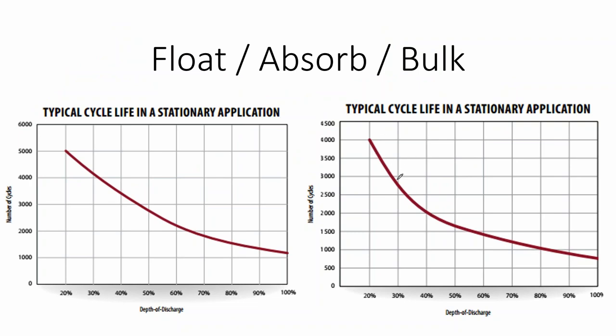If we look at these two batteries in the manufacturer spec, on this lower end battery, you don't want to cycle it down more than about 35% on a regular basis, because once it gets into this deeper range, it's not that the battery won't work. It'll still provide power, but the life of the battery starts to substantially diminish.